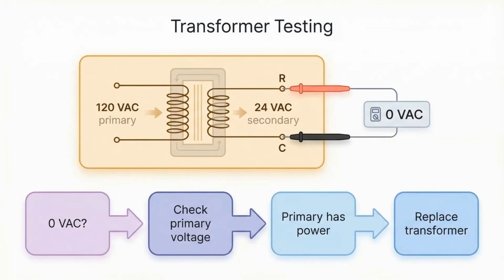Transformers step line voltage down to 24 VAC for low-voltage controls like gas valves. Testing is done with a multimeter set to AC volts. Measure the low-voltage side across R and C. If it reads 0, don't assume it's dead immediately. Check the primary side for line voltage. If the primary has power but the secondary is 0, then the transformer needs replacement.